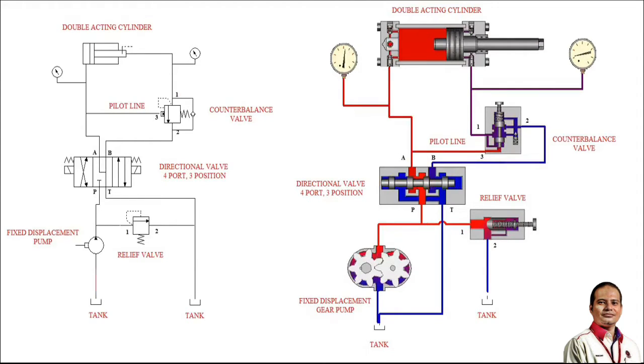See, if I go back a frame, when this was shifted over, this was exposed to pump pressure. Now, when I shift the spool, all of a sudden A is going to be vented, if you will, back to tank, but P is still going to be at the high pressure. So at this point, although we've shifted our spool back to center, still all of our pump flow is going to be going over relief because there's nowhere else for this pump flow to go.